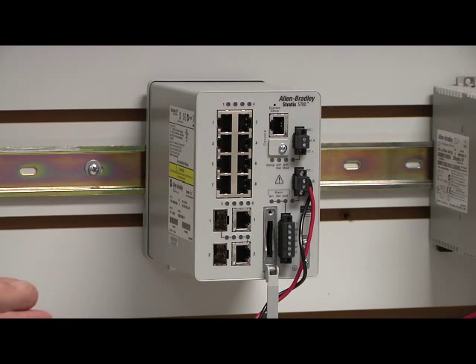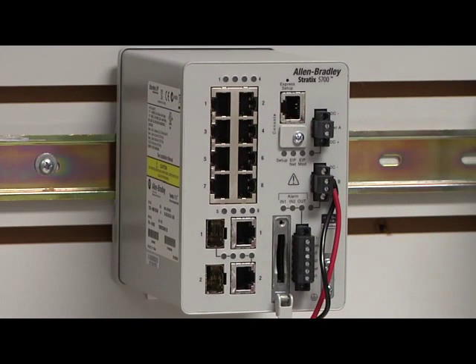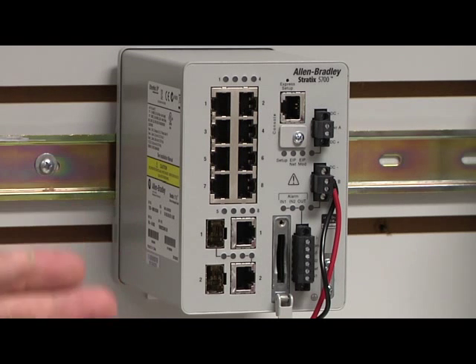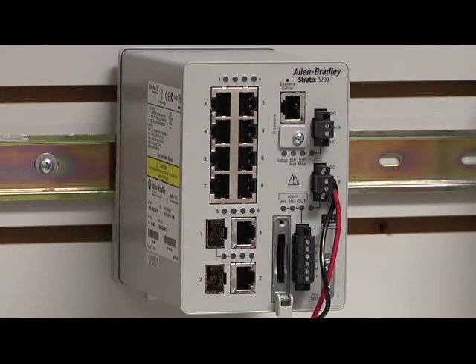The Stratix 5700 can be loaded from the SD card. It's important to note that Stratix 5700 has the DHCP persistence feature. This is important when using automatic device configuration in drives such as the PowerFlex 525 or the Kinetix 350. It automatically assigns the IP addresses so that the CompactLogix program can automatically download the parameters.